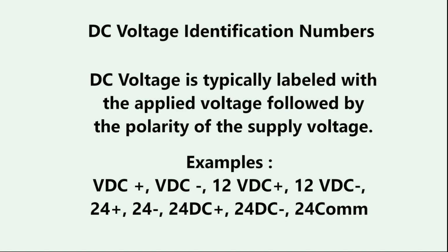And again, sometimes we'll put the voltage on there. It could be 12 volts DC plus, it could be 24 volts DC, it could be 36 volts DC, 48 volts DC, whatever the voltage is, but it is usually always marked with the DC and a plus or a minus, or just plain DC and common. In that case, the plain DC would be the hot and 24 common would be the common wire.